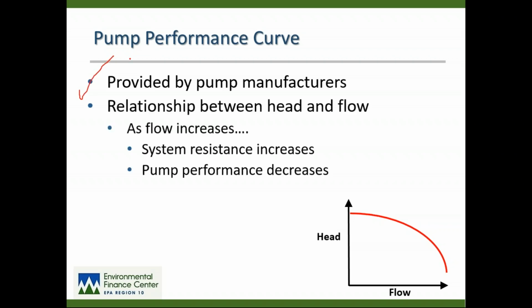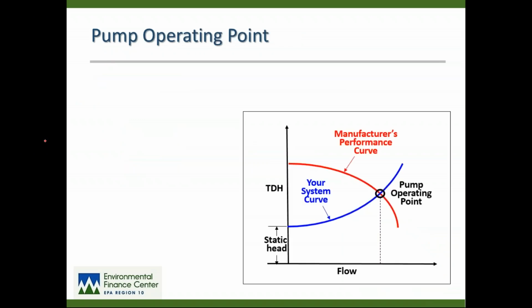The pump performance curve is provided to you by the pump manufacturer. It's the relationship between head and flow. Head being total dynamic head on this axis. All pump curves are pretty much the same, manufacturer's curve, as a function of gallons per minute or liters per minute on this axis down here. As the pump ramps up and flow increases, system resistance increases, resistance being dynamic head, and pump performance decreases. So basically, the more water we are trying to push through the pump, the performance of the pump decreases proportionally.